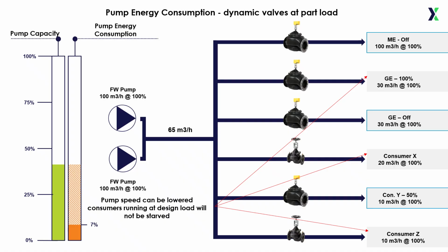As a result, pump energy consumption drops dramatically, in the shown scenario down to just 7%. This example highlights how dynamic valve technology enables safe reduction of pump speed without risking starvation of critical consumers. Thereby, significant energy savings are unlocked with improved efficiency and lower operating cost as a result.